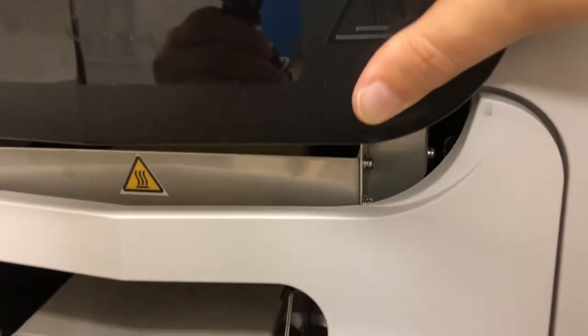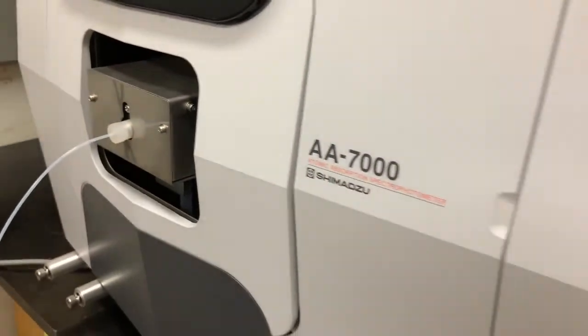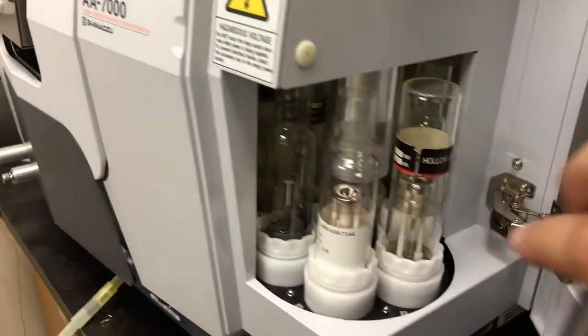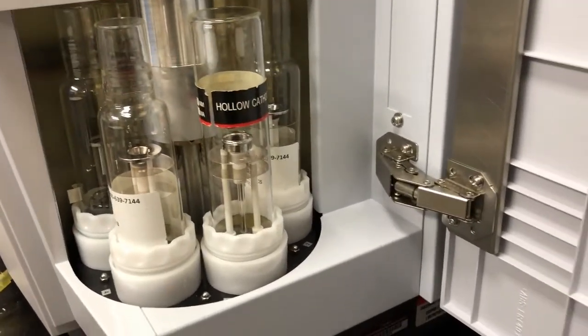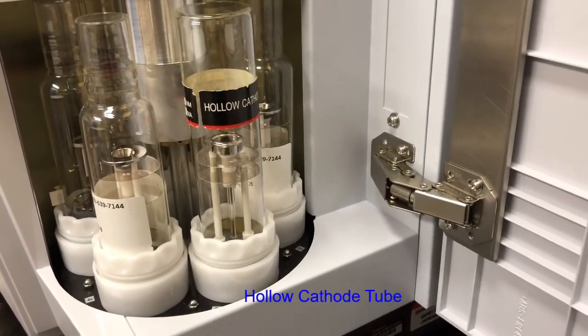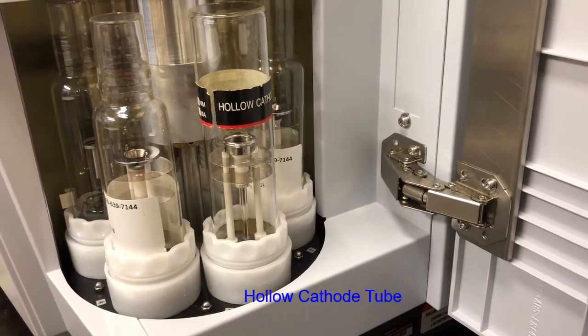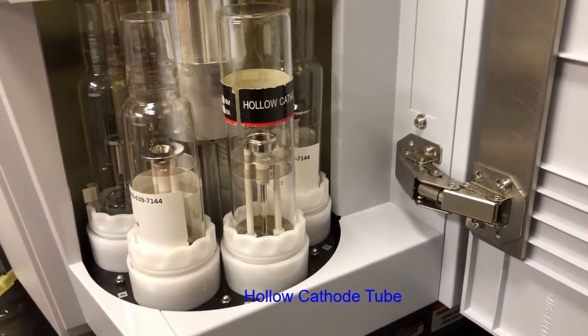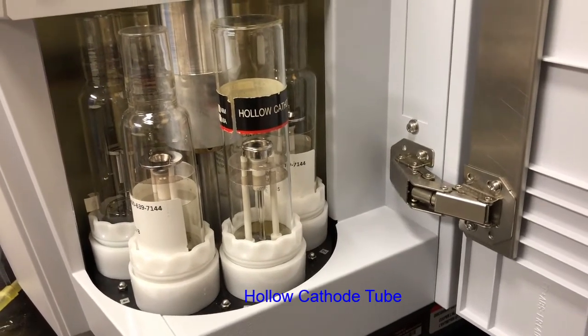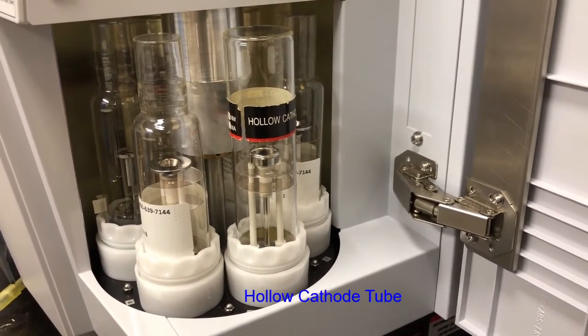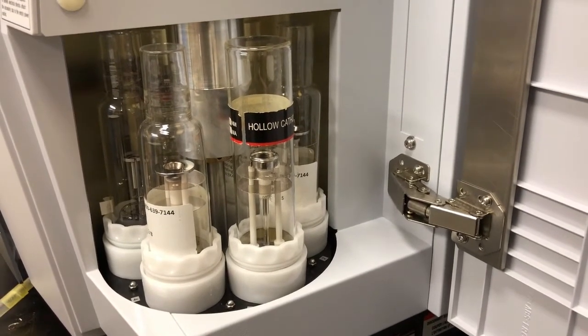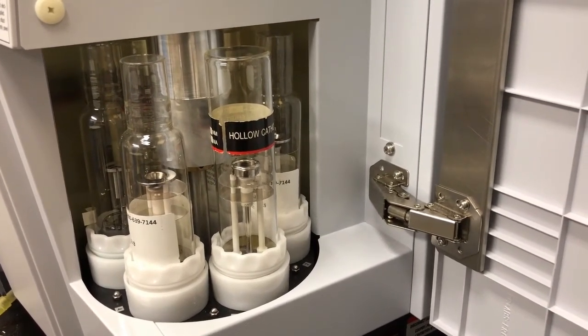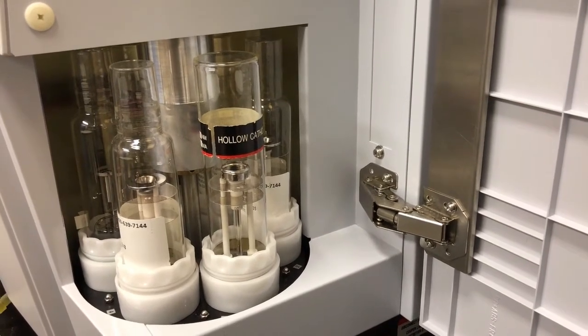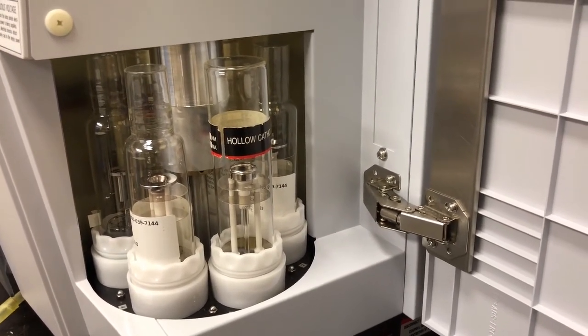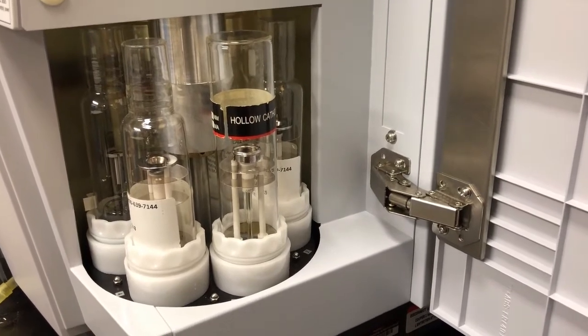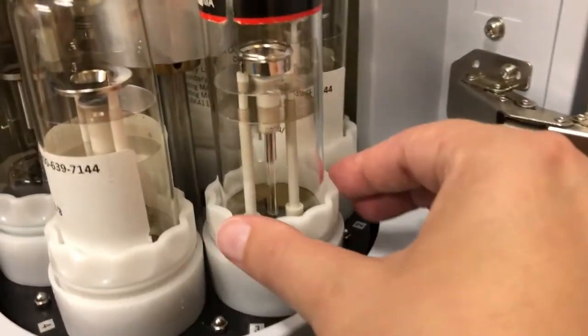Okay? So we have lamps in this unit. Come over here on this side, there's a little door, and that's where our hollow cathode tubes are. So we have these lamps for every element that we're going to test. So if we're testing iron, for example, we would have a hollow cathode tube lamp specific for iron. So these hollow cathode tubes contain the element that we're interested in, and it emits radiation at the same wavelength as the light of the element that we're interested in. So we have these specific for each element that we're looking for.